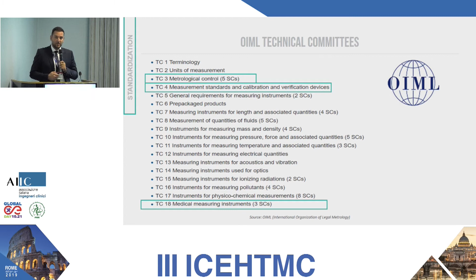As a solution, when we checked it all, we found out that the solution will be this. So we have, as we started at the beginning, medical device, metrology and standardization. The basics and the most important aspects are safety, performance, accuracy and reliability. How to get performance and accuracy: by doing inspection, which is defined in metrology, which is defined by the standard ISO 17020. If we are talking about how to perform inspection by having etalons, those etalons must be calibrated with established traceability. How will we establish it? By using the ISO/IEC 17025 standard. How to get safety? By using 60601.